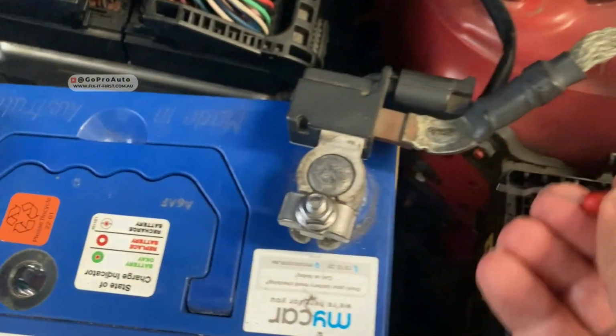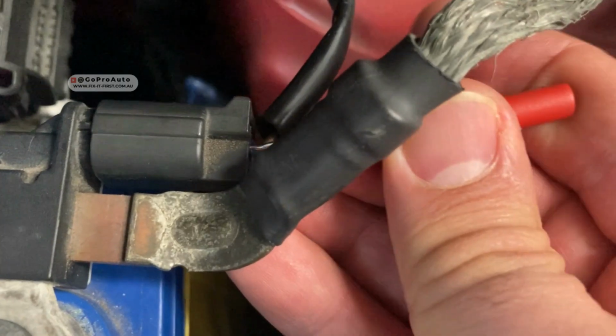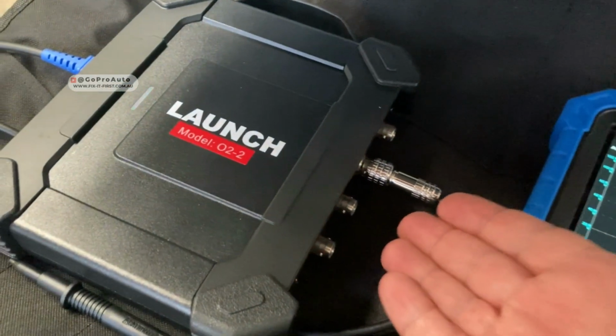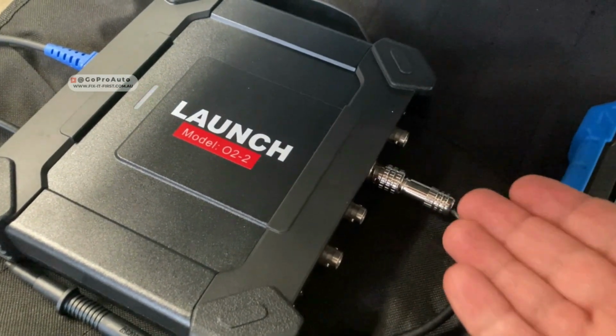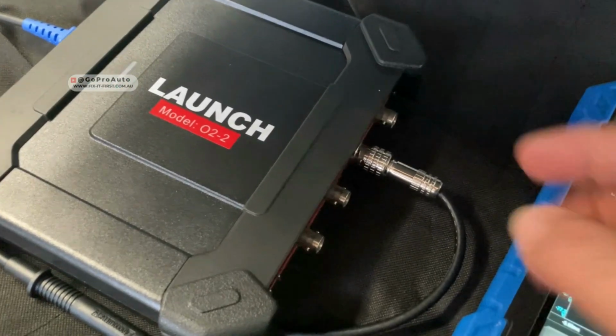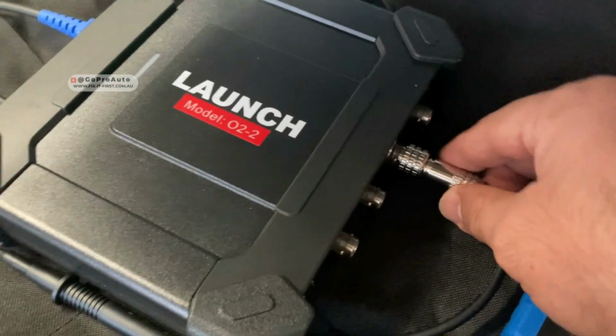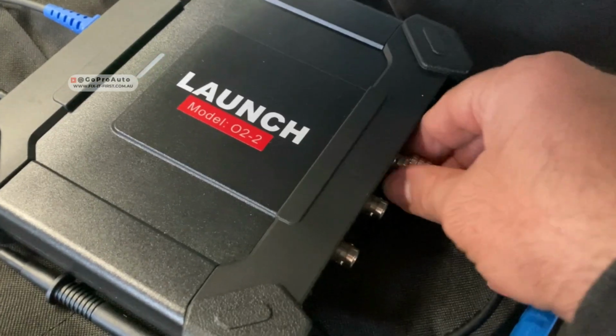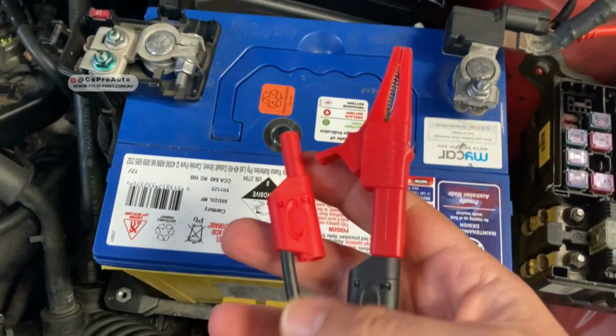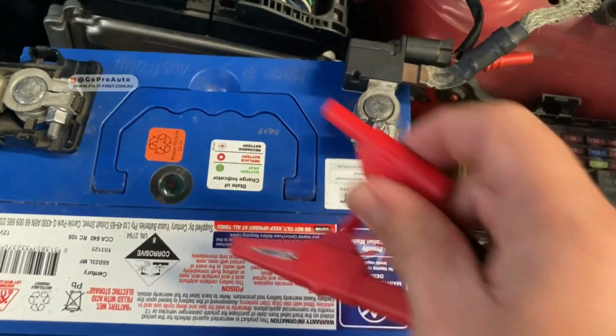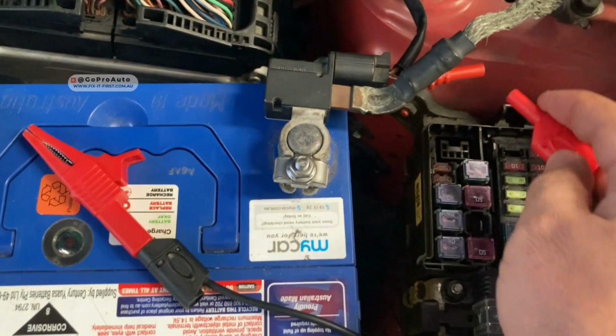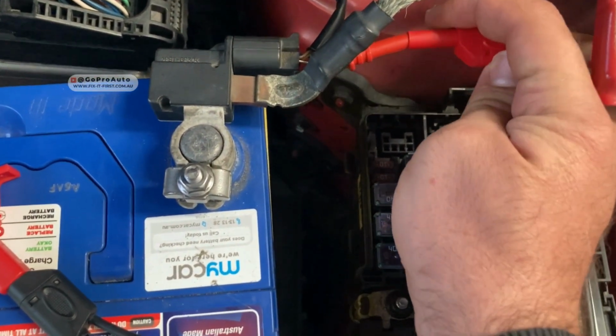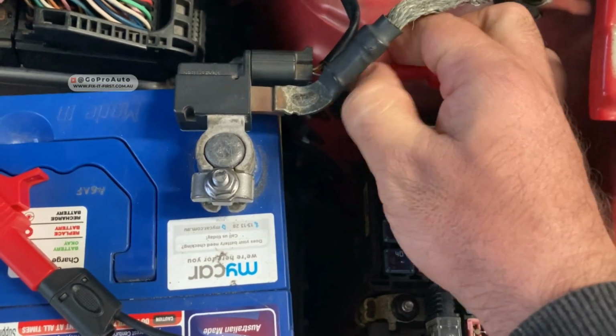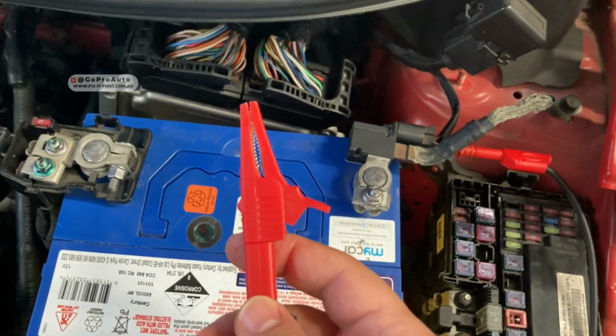I'm going to use one of these test probes. We are only using one channel on the oscilloscope because this network has only one wire, so I'm using channel 2. One end of the probe is already connected to the scope box. On the other end I have these two: this one is for picking up the signal, so I need to connect it to the test probe, and this one is for a good ground.